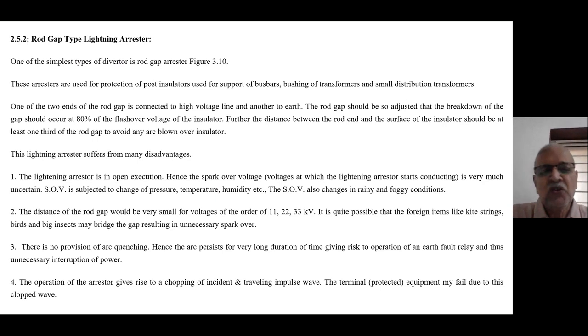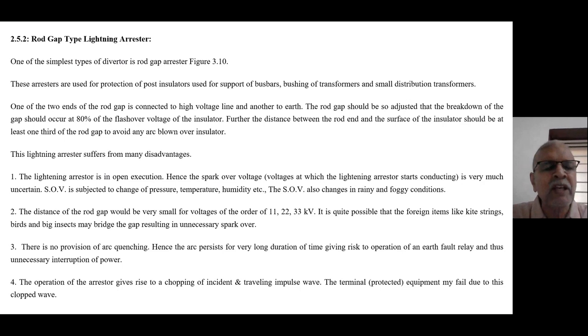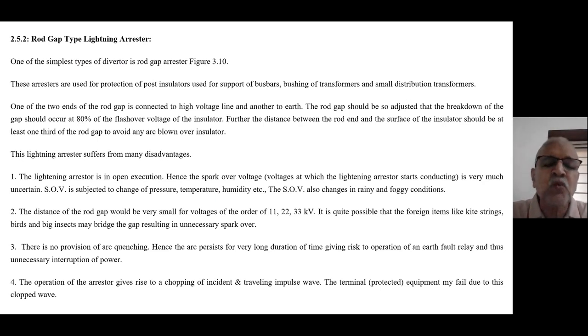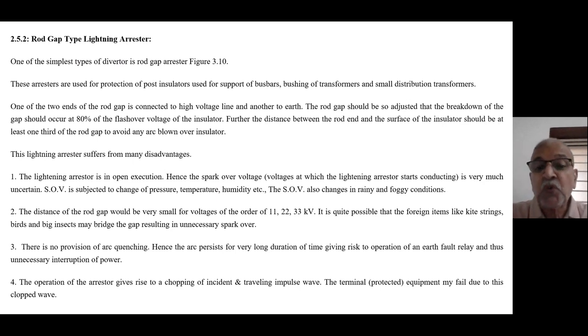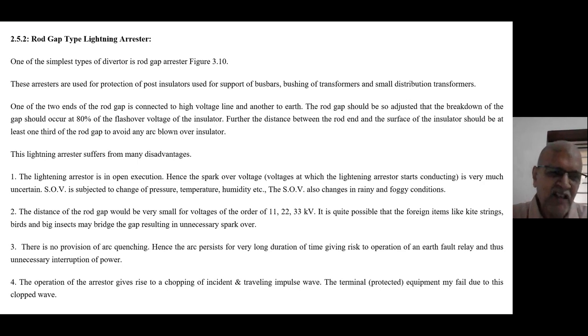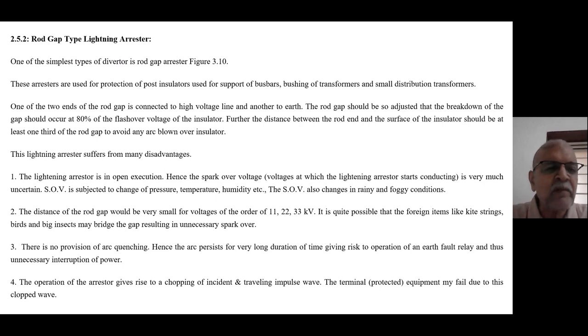It is in open execution — so it is subjected to moisture, rain, everything. The overvoltage at which it sparks over is not fixed, and therefore it may mal-operate and cause trouble. The second problem is the distance in the gap: the distance between the rod gap is one-third of the height of the bushing. But for 11 kV, 22 kV, 33 kV the bushing is very small, so one-third of that is a very small distance.